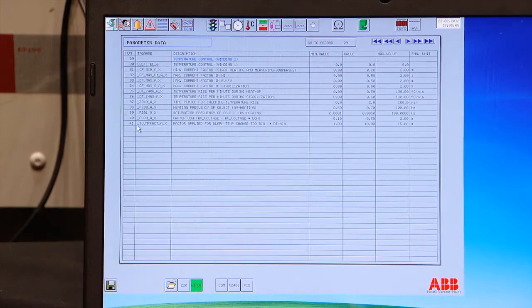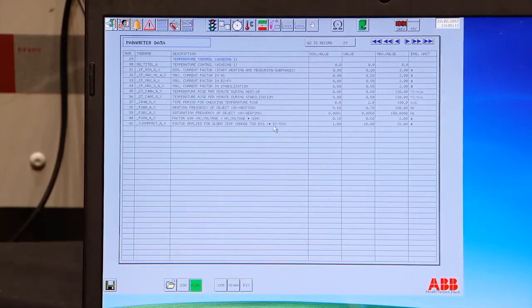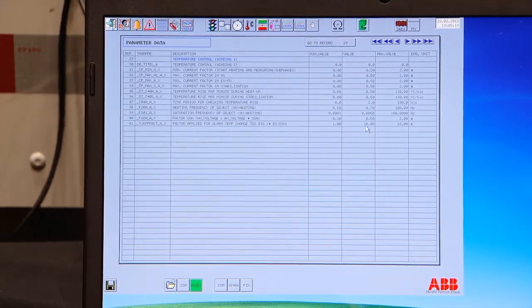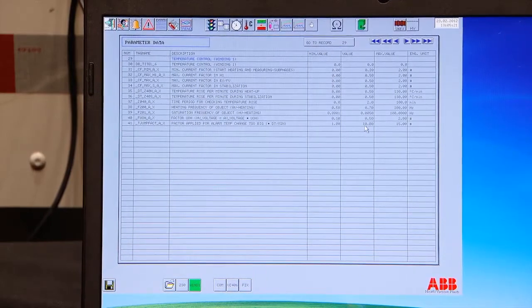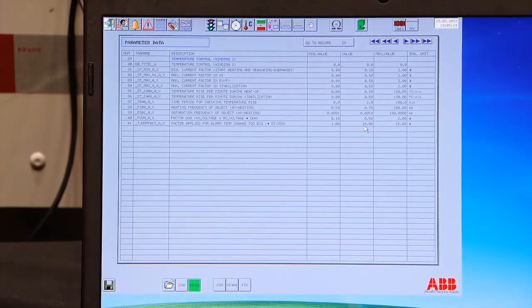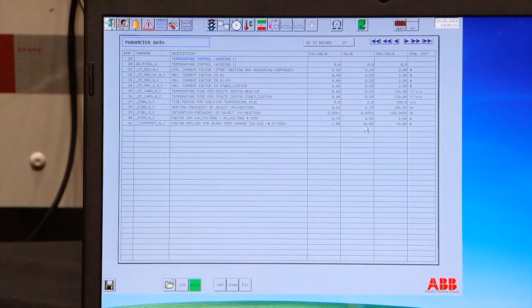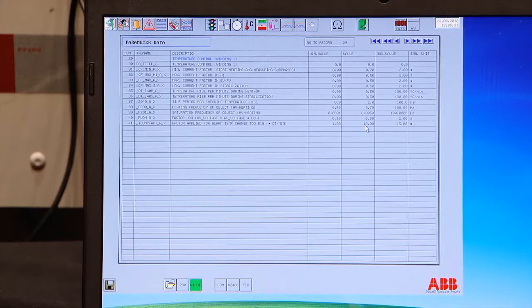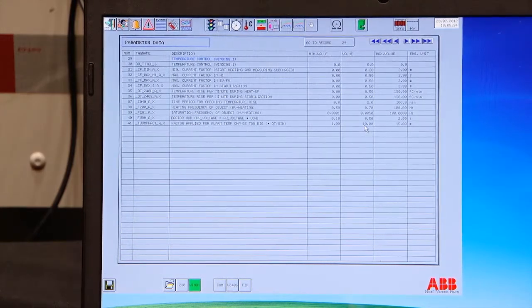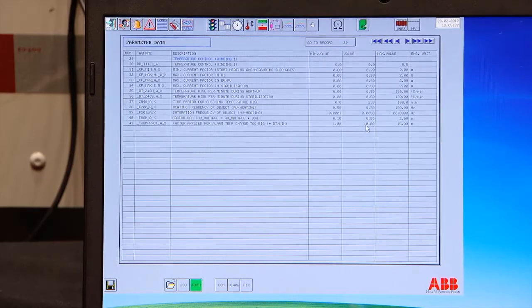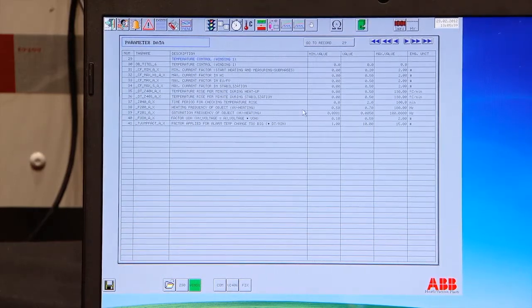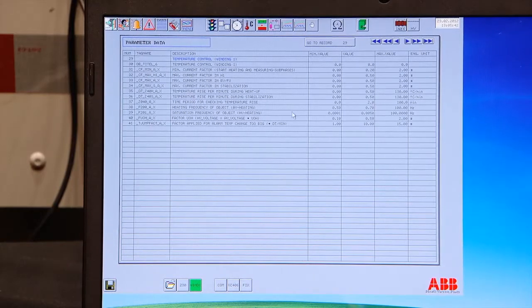We have this parameter, T jump factor, applied for an alarm if the temperature changes too fast, in degrees per minute. So if the temperature changes 10 degrees per minute, then you will have an alarm. That's a huge step. I mean, then something has happened. That's when the bus bar is melting on the secondary side, because it is impossible for the temperature to change so fast. You have 100 tons of steel, it cannot change that fast.